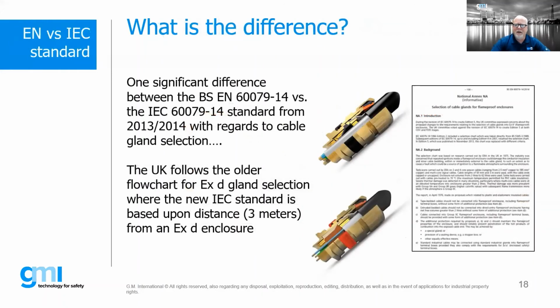This is an example, these two pictures here. This is considered to be a non-barrier type. So what you have is an inner seal, but this is an elastomeric seal. This is a brand called Hawke that makes what is called a diaphragm seal, and that seal is actually a flame-proof seal, but it's an elastomeric seal. That's not to be confused with the back seal, which is providing ingress protection and pull-out strength.